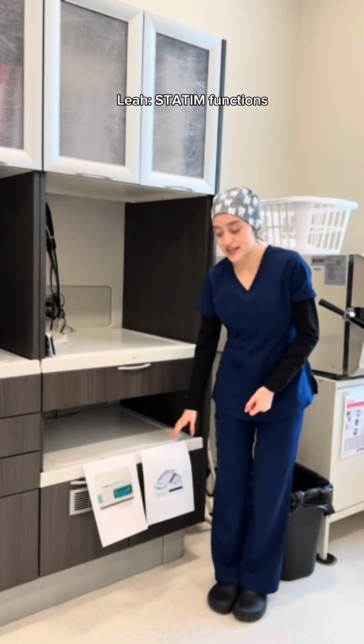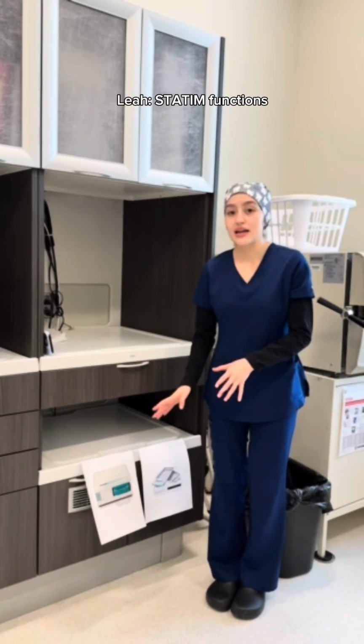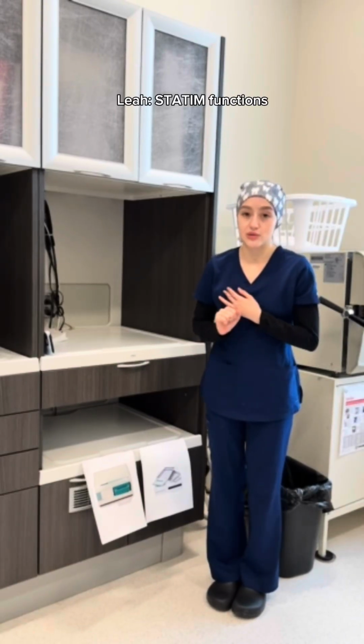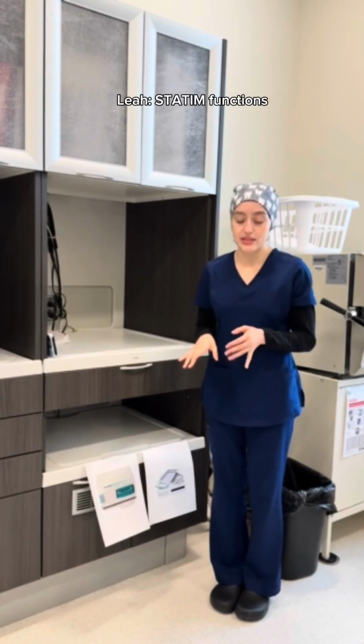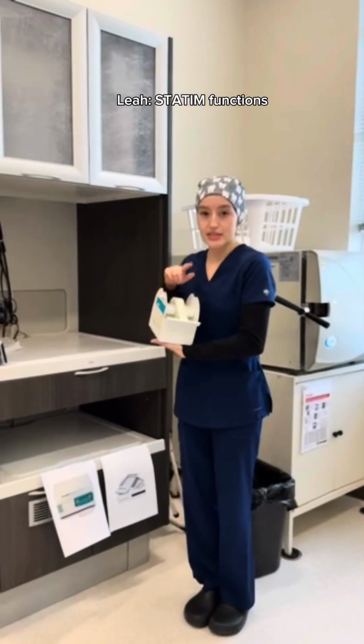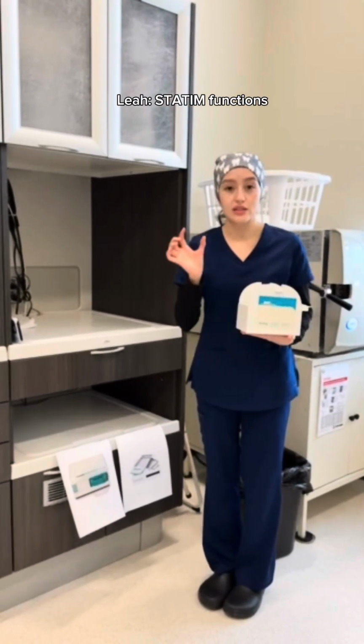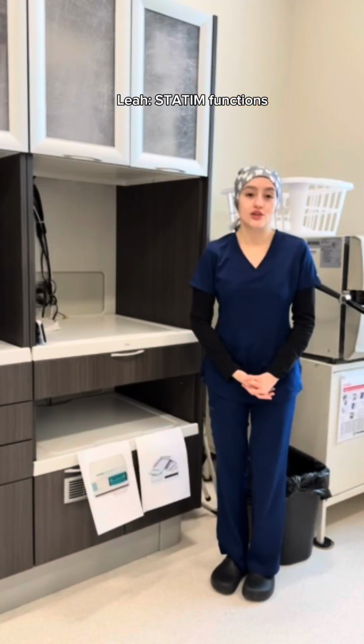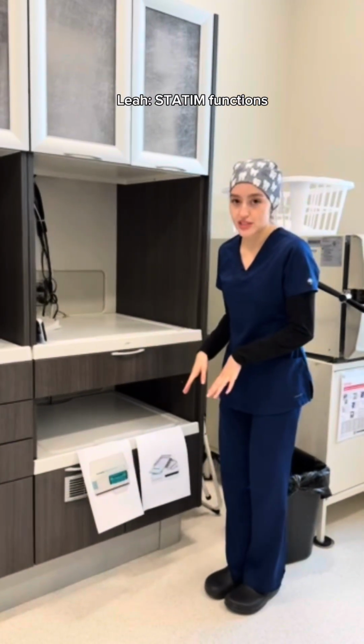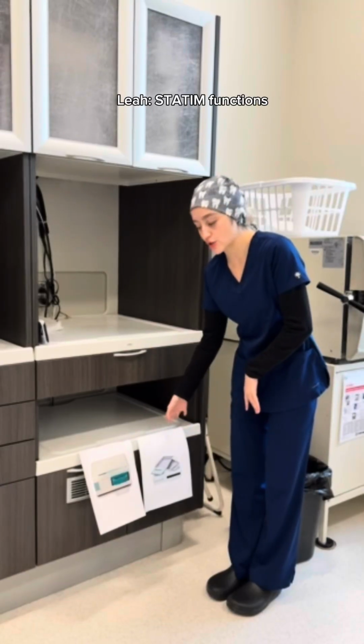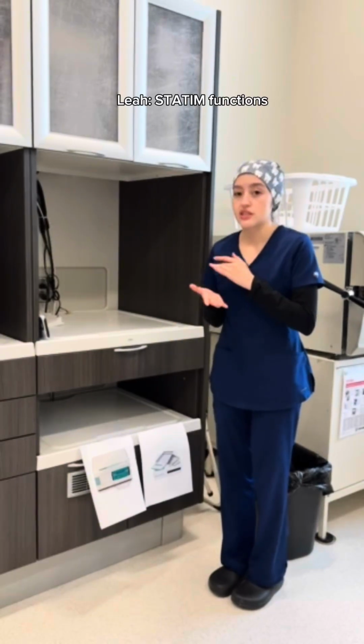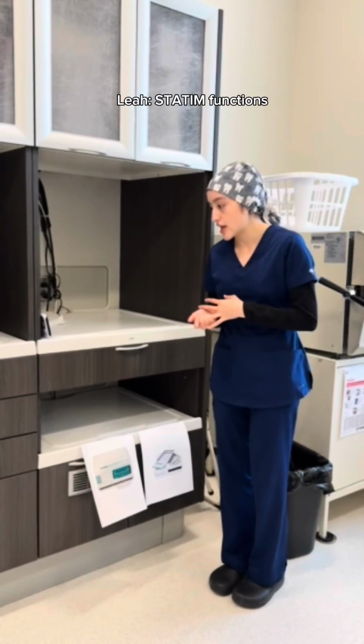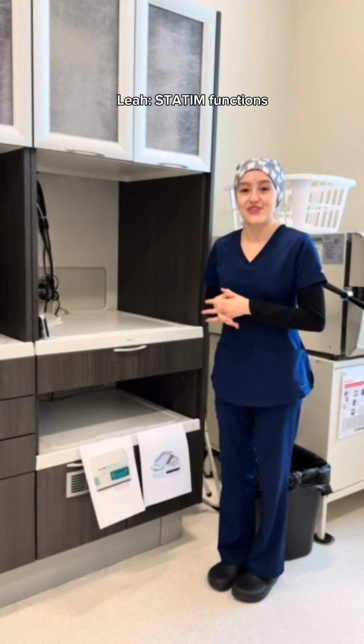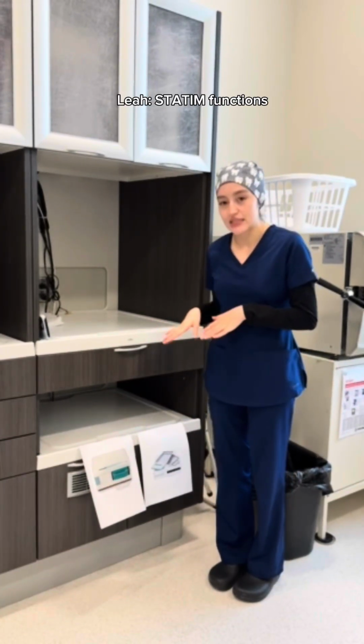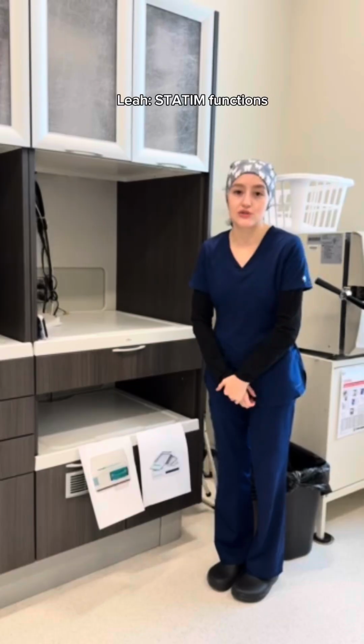After the cycle is done, then I will take the cassettes out and I will check the indicator strips to make sure they were sterilized properly. There's going to be two different methods. So the two different methods are going to be the tape indicator or a little strip that you put into the cassettes. So for daily maintenance, you're just going to wipe down the machine, empty the tanks, make sure they're clean, the dirty one and the clean one. And then for routine maintenance, that isn't as often, we're just going to check the seals, we're going to check the filters, and then replace them if they are needed. Following these procedures can make sure that the Statim stays clean and works efficiently for the next person to use.